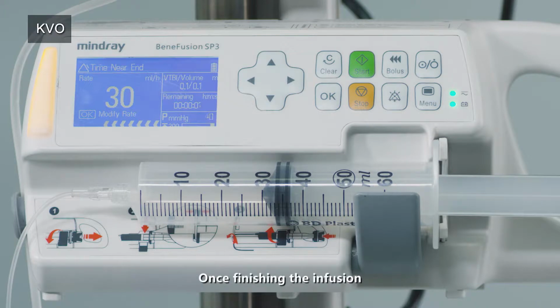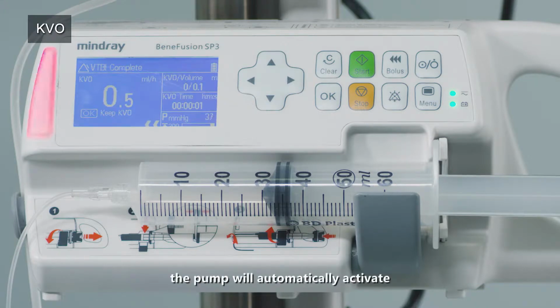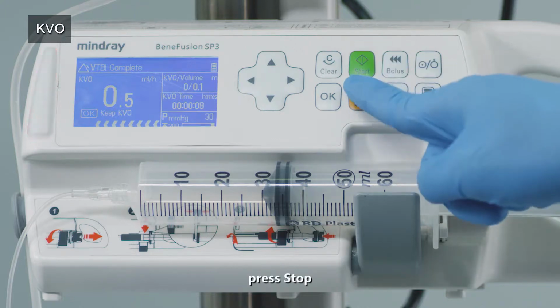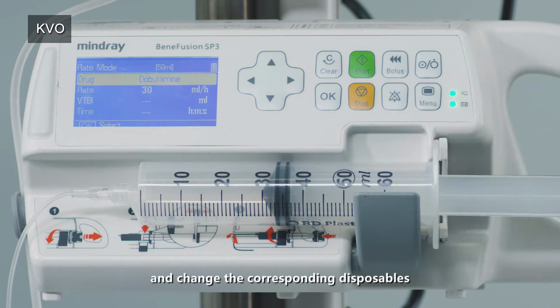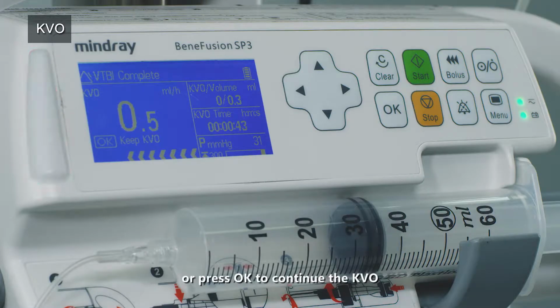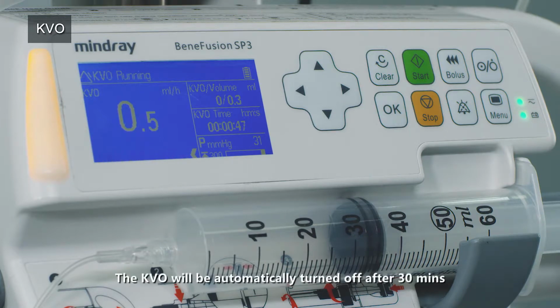Once finishing the infusion, the pump will automatically activate the KVO mode. If you want to turn off the KVO, press Stop and change the corresponding disposables, or press OK to continue the KVO. The KVO will be automatically turned off after 30 minutes, which indicates the infusion has been completed.